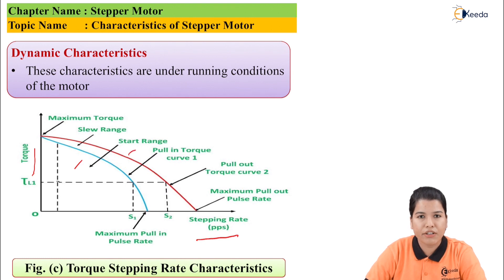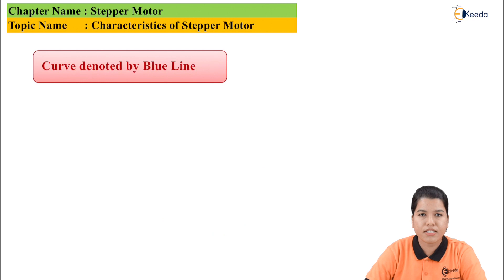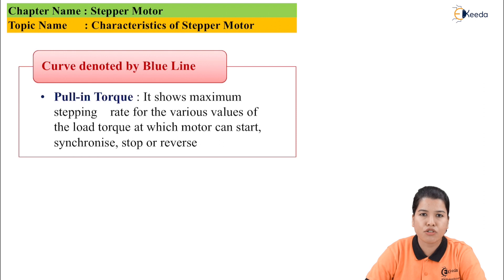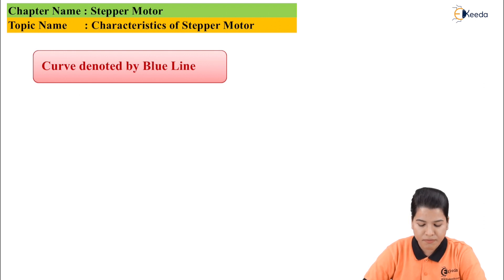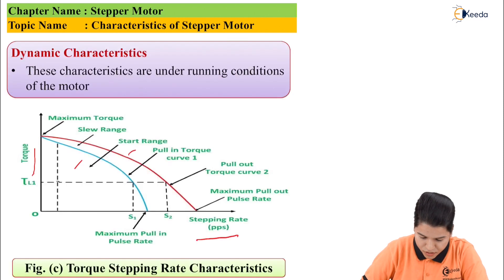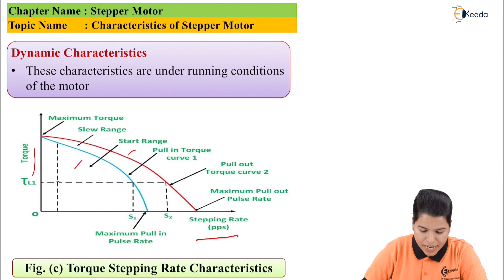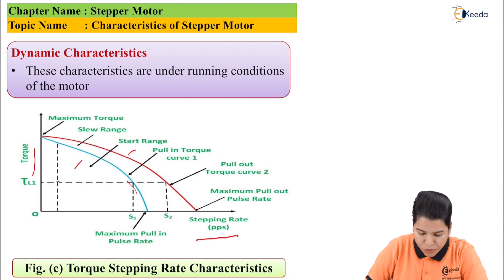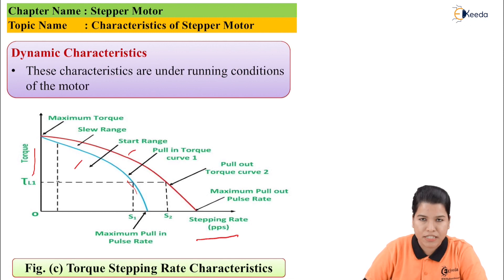Now let us see the significance of these curves. The curve denoted by the blue line is called pull-in torque. Pull-in torque represents the maximum value of torque at which the motor can start, stop, synchronize, or reverse. This blue curve denotes the pull-in torque, and at this value the motor can start, stop, synchronize, or reverse up to the maximum pulse rate S1.